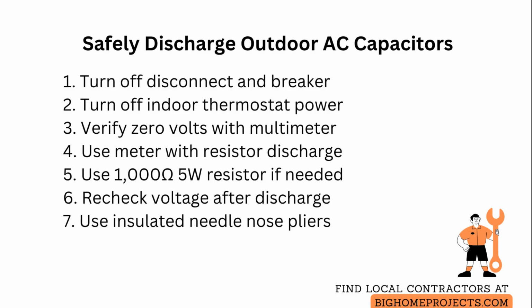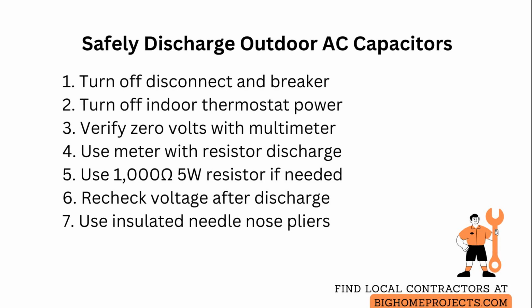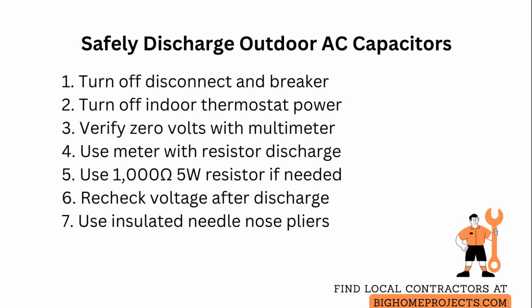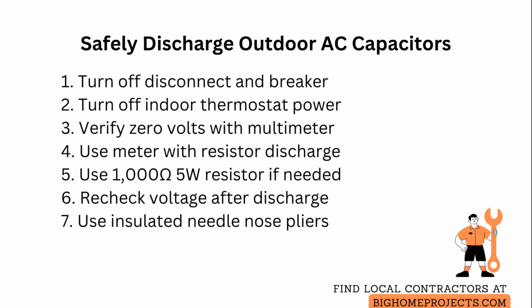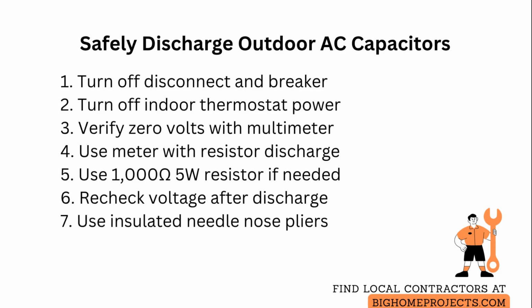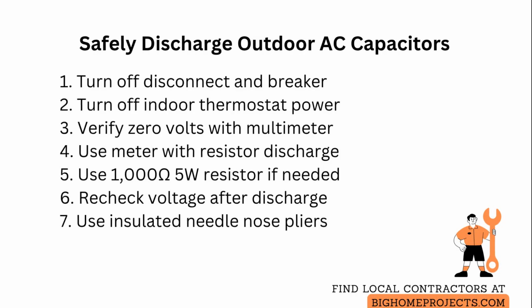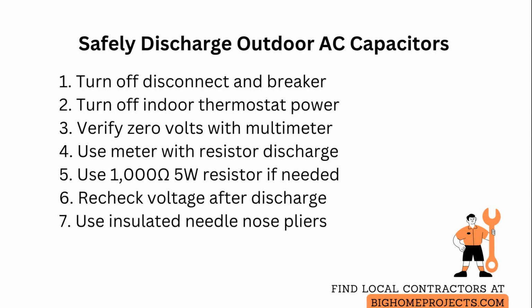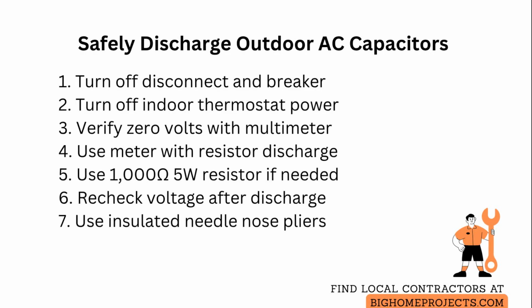If the meter shows charge, use a meter that includes a built-in resistor discharge function and place the meter leads across the terminals to bleed charge slowly and safely. If your meter does not have that feature, prepare a professional resistor discharge tool such as a 1000 ohm 5-watt resistor attached to insulated leads and clamp it across the terminals for several seconds while holding the insulated handles. Never short the terminals with a screwdriver because that can cause sparks and damage.